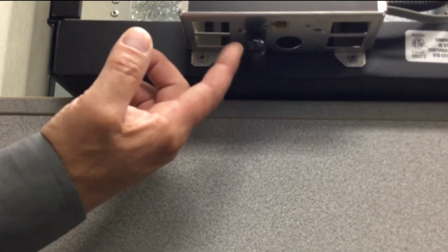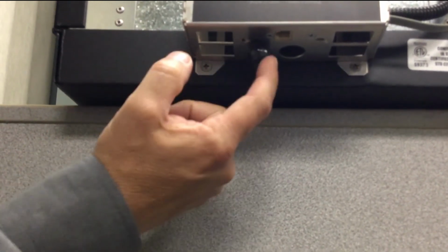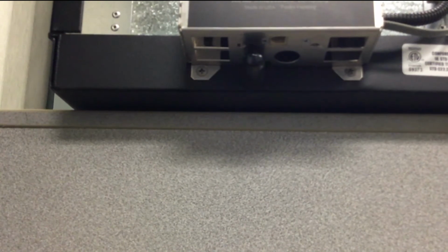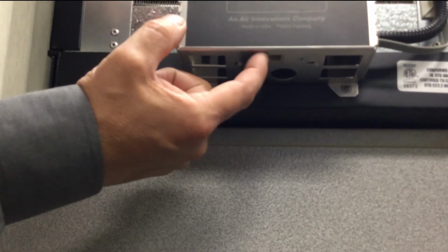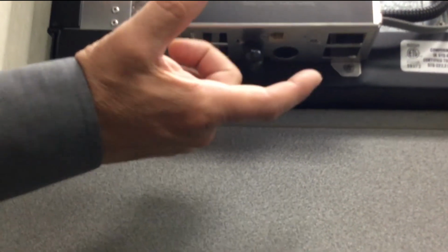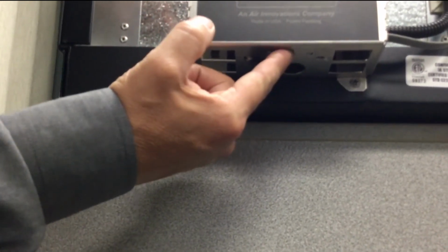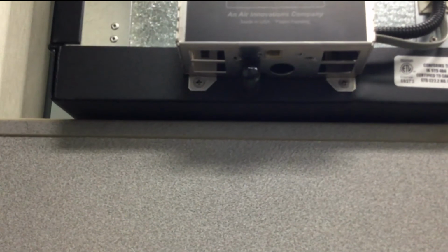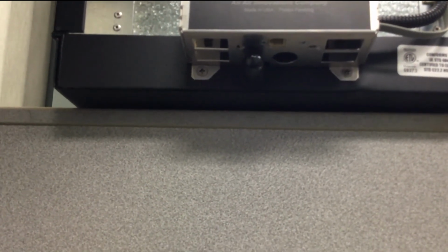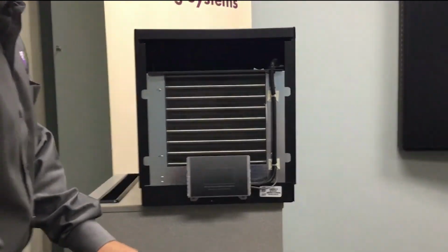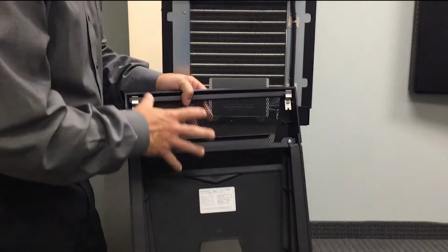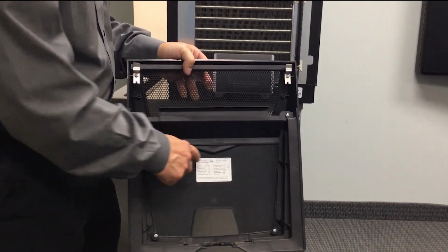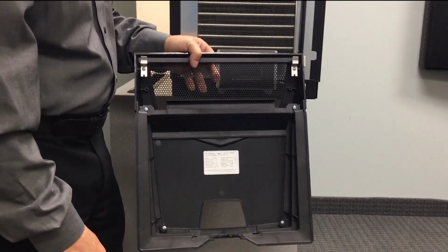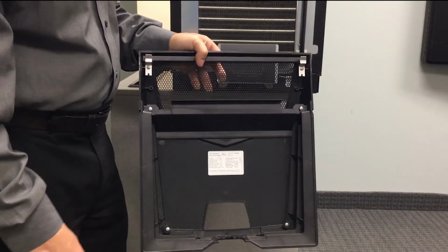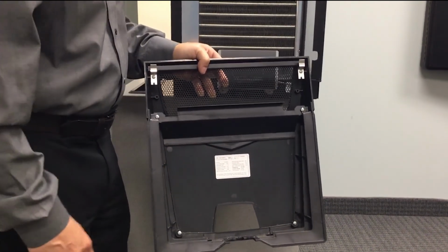In addition to that, at the very bottom underneath this control panel here, there's an electrical connection for plug-in of our auxiliary controls. If you had a remote sensor or our remote thermostat, what we call our remote interface controller, this is where you'd make that connection. This is where you'd plug that in and then wire that out to wherever you wanted to mount those remote sensors or remote thermostat. In addition to those connections, just one thing to point out: on the back of our faceplates, you'll have your serial plate, which will give you all the pertinent electrical information, the serial number, the part number, all of the amp draws, and so forth. So if you need that information, it's on the back of the cover plate.